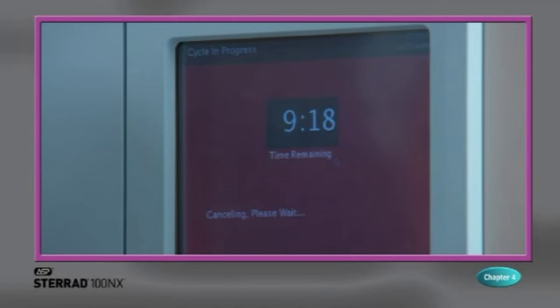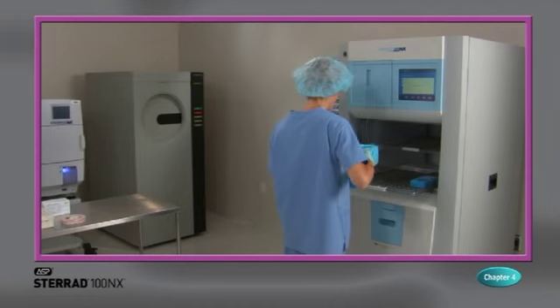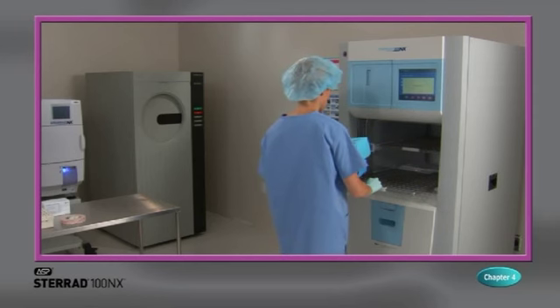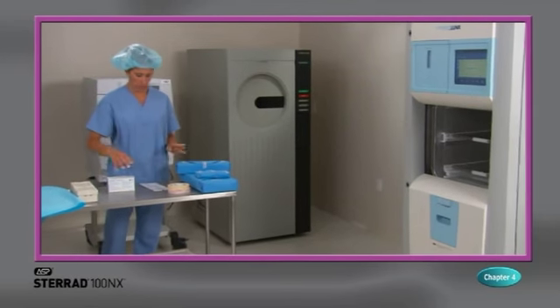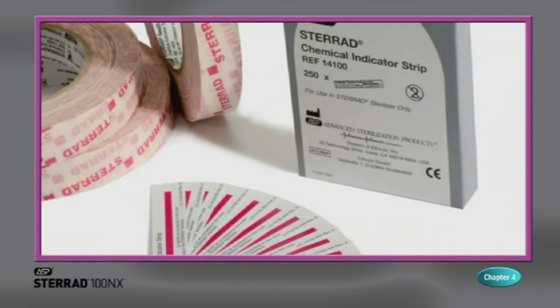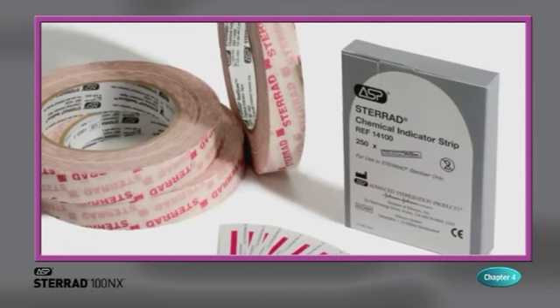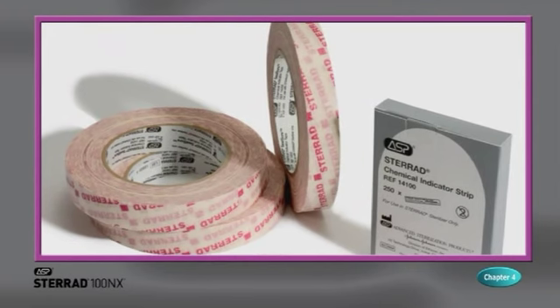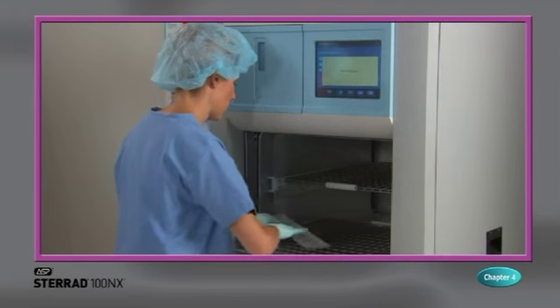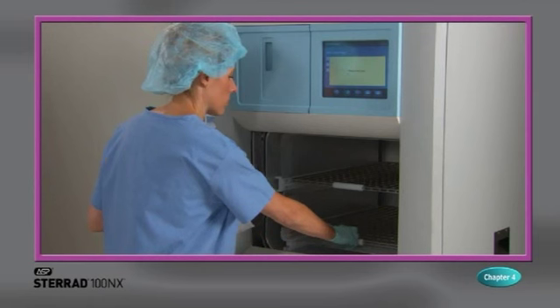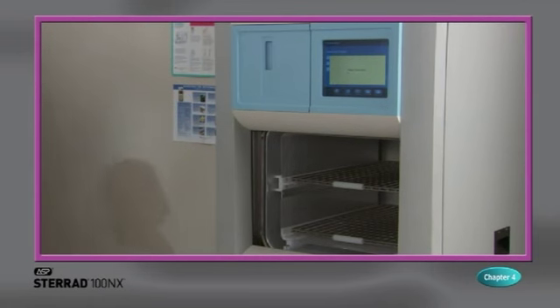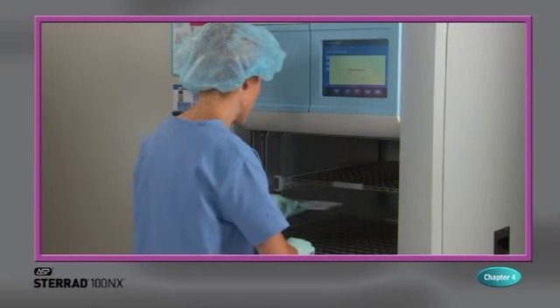Once the cycle cancellation sequence begins, the screen turns red and the cancellation sequence cannot be interrupted. The cancellation sequence may take up to 10 minutes to complete. Gloves must be worn to remove items in a canceled cycle. All instruments must be rewrapped using new packaging materials, Sterrad chemical indicator strips, and Sterrad Seal Sure chemical indicator tape. If a biological indicator was used in the canceled load, the previously used biological indicator must be discarded, and a new biological indicator must be placed in the chamber before restarting the new cycle.